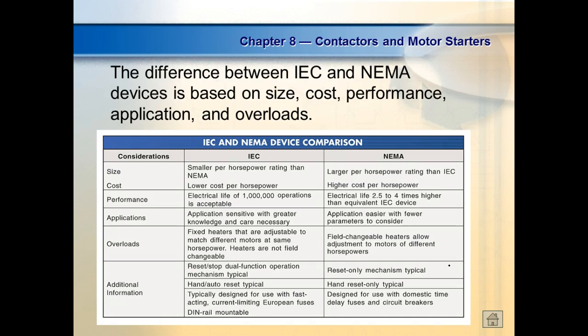So eventually they realized that it would be better for everybody if somebody comes out and does what? Sets standards. This is the way we're going to do it, and everybody does it the same way. So that's why you can go to Lowe's and buy a standard outlet. You could buy what we call a NEMA 5, which is this two-bladed connector or the three-bladed connector you see. So it's got two blades, and then it's got a ground, right? And one blade is longer than the other. That's a NEMA connector. And this is what we call a NEMA 5. And then we have a NEMA 5-15, which is a 15-amp plug. And then we have a NEMA 5-20, which is a 20-amp plug. What they did on the 20 is they put a little notch on the side right here.